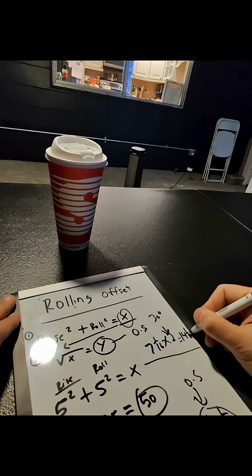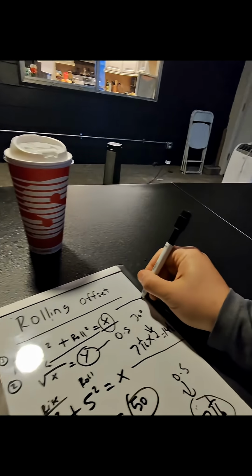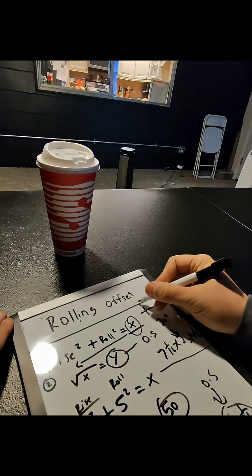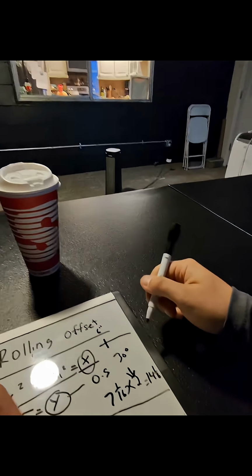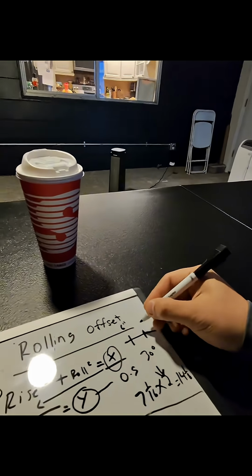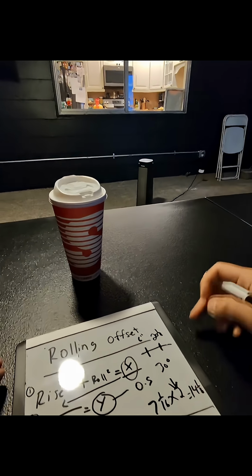Pretty straightforward. So let's assume this is our conduit. Our first mark, let's just say we assume it's at 6 inches. Then we found our spacing, a 7 1/16 offset with our multiplier, 14 1/8 spacing. So our second mark would be at 6 plus 14 1/8, which is 20 1/8. Both of our marks found.